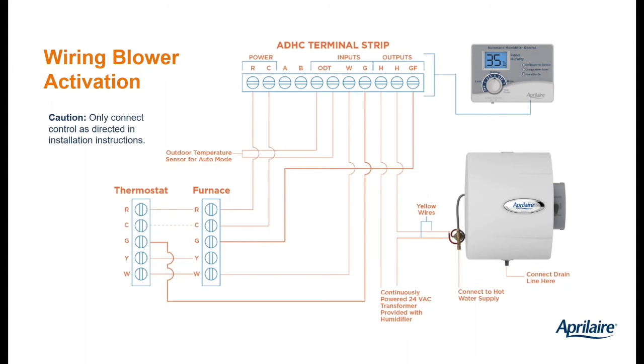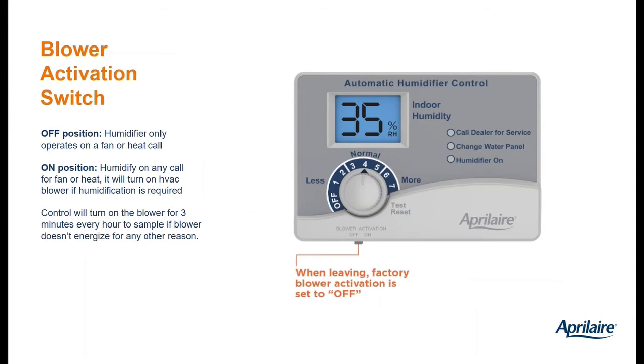But it also lets the humidistat make a fan call. That's the key to this. It lets the humidistat make a fan call. So we can get lots more run time than just having to wait for the thermostat to call for fan or the thermostat to call for heat. And that last feature allows us to utilize our blower activation. So you see at the bottom there, there's a switch. It says blower activation, off and on.